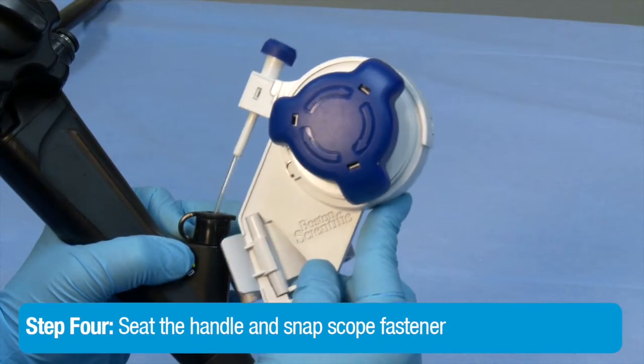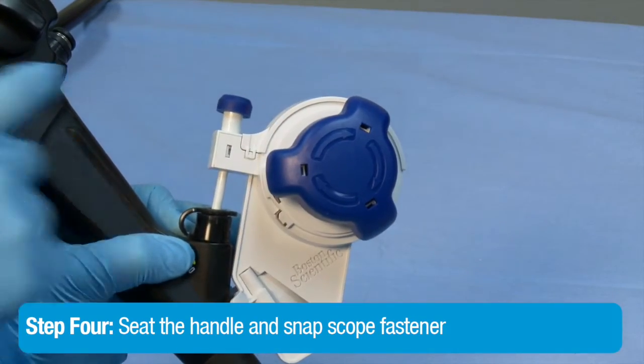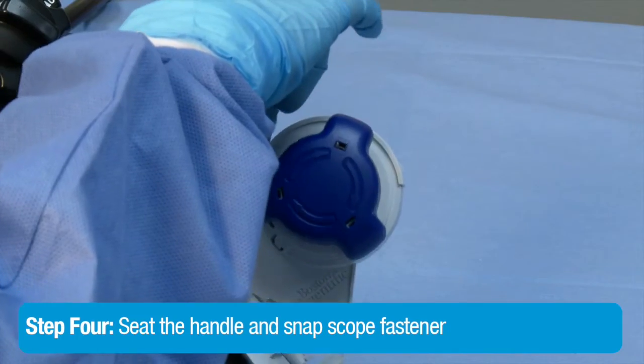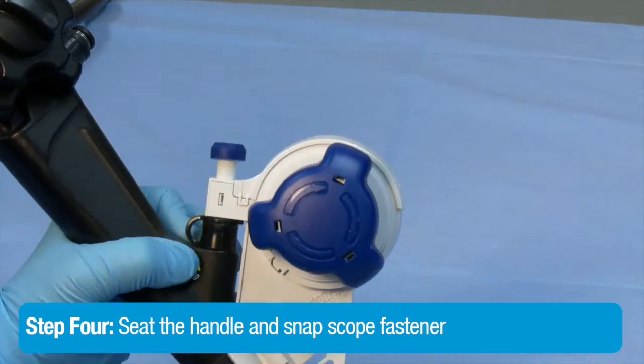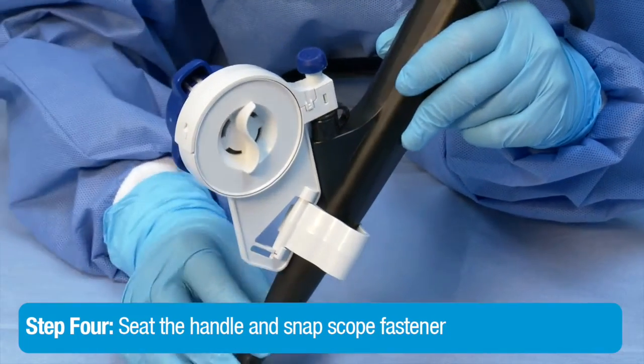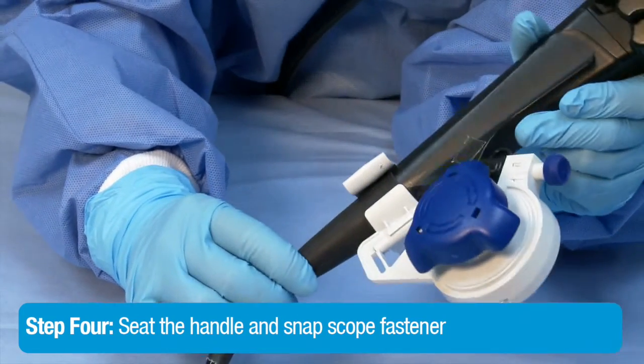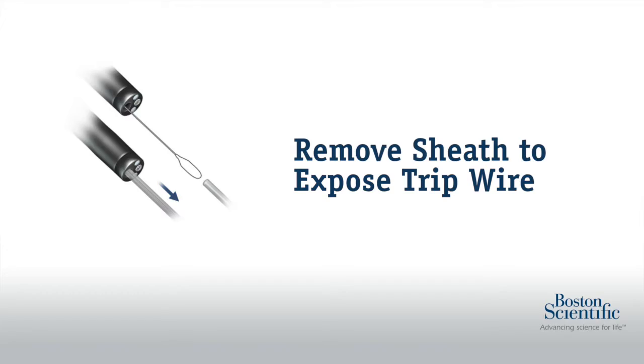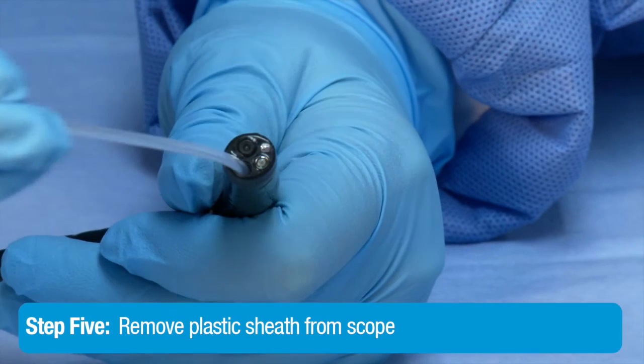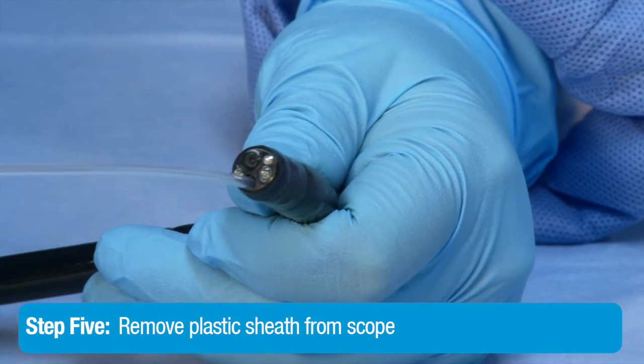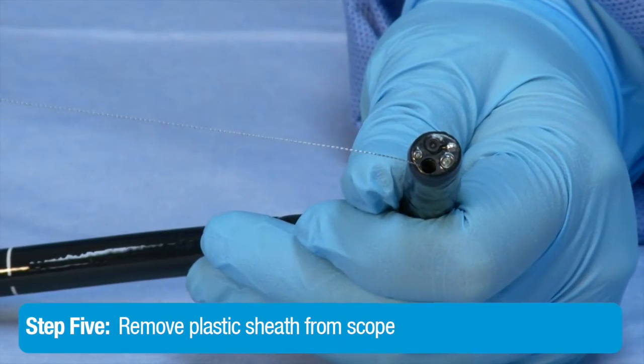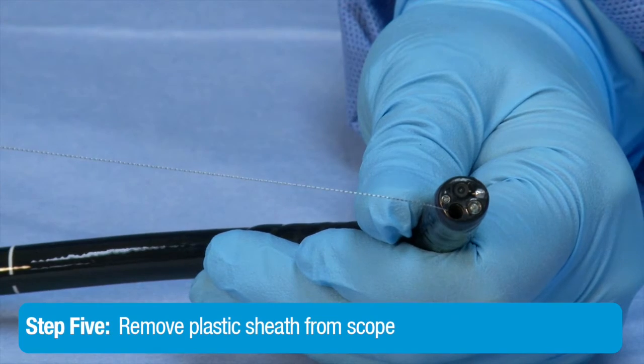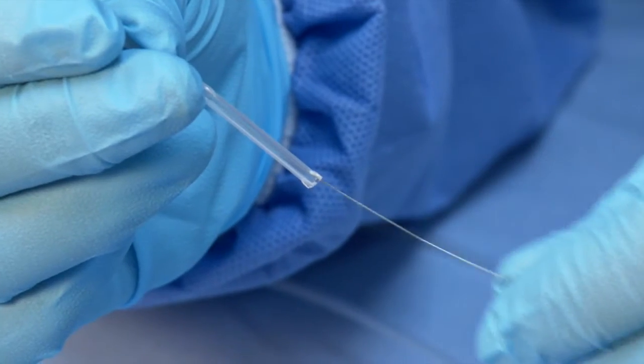Make sure to firmly seat the handle into the biopsy cap and snap the scope fastener onto the endoscope. Next, we're going to remove the sheath to expose the tripwire. Remove the plastic sheath from the scope by pulling it from the distal end of the endoscope until it is fully detached and the metal tripwire is visible. You can go ahead and discard the plastic sheath.